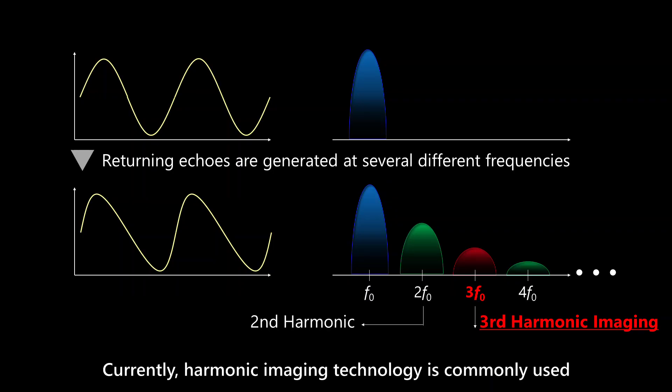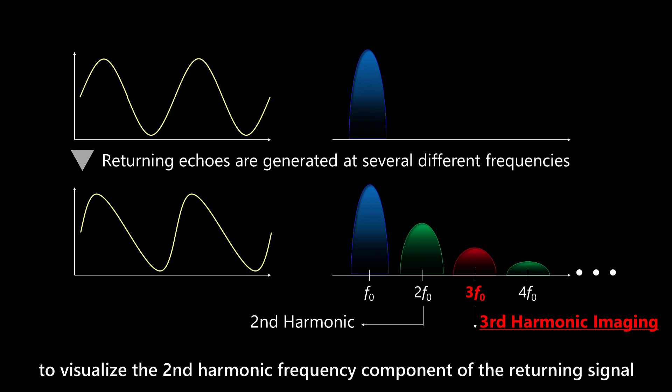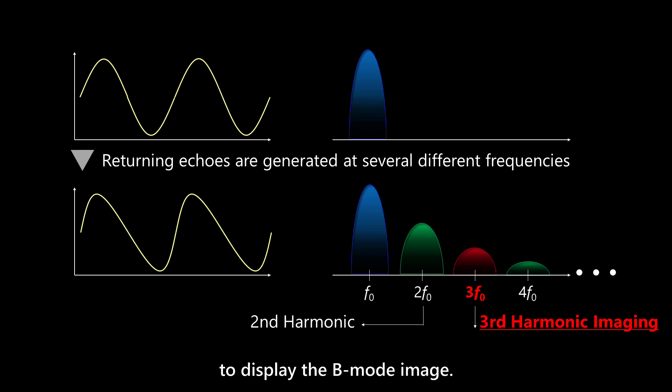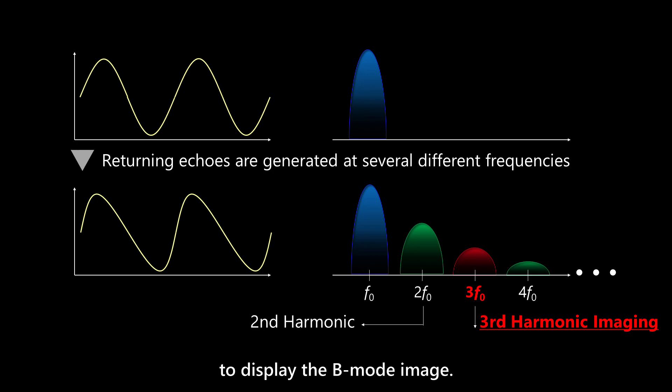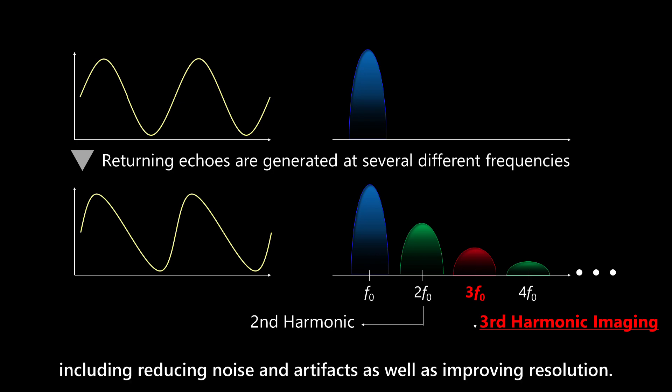Currently, harmonic imaging technology is commonly used to visualize the second harmonic frequency component of the returning signal to display the B-mode image. There are many benefits to using the second harmonic, including reducing noise and artifacts, as well as improving resolution.